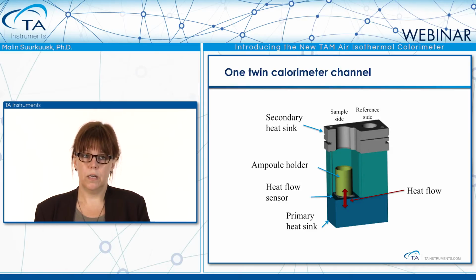All other surfaces around the ampule holder and the ampule are air, so that's isolation, which means that we channel the heat flow to go through the heat flow sensor in the bottom. This is the sample side you are seeing cut away, but the reference side looks identical. In the reference, you will have an inert sample. You will match it by heat capacity, but there should be absolutely nothing happening in the reference.